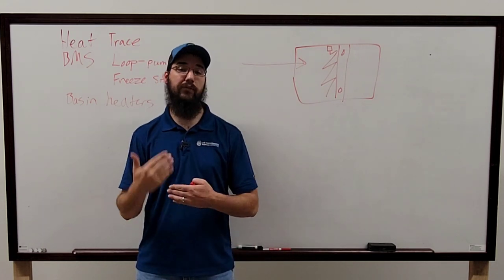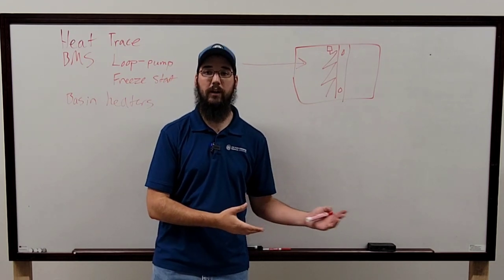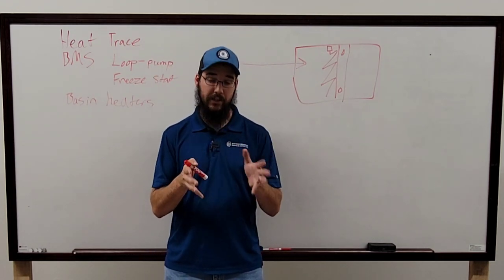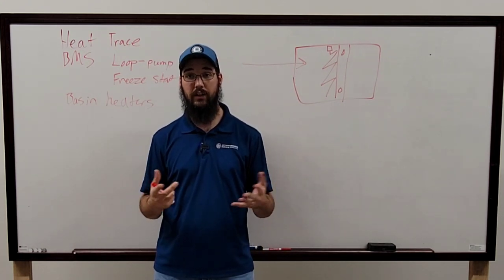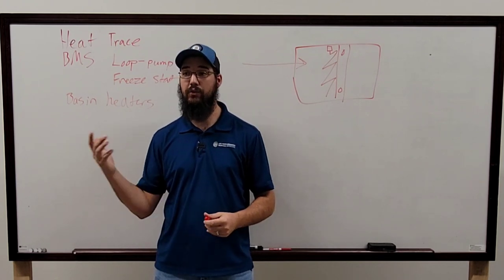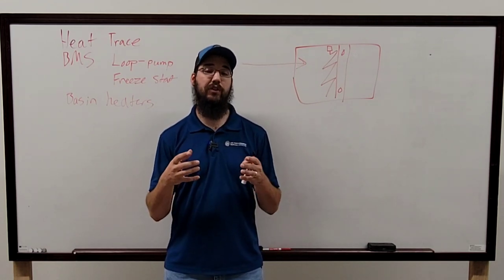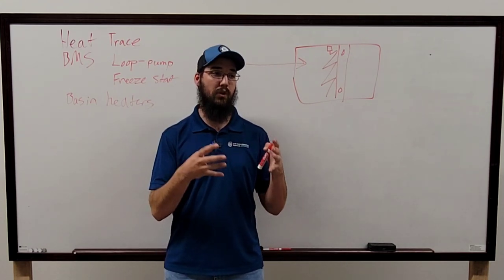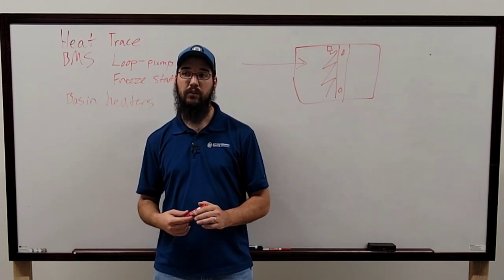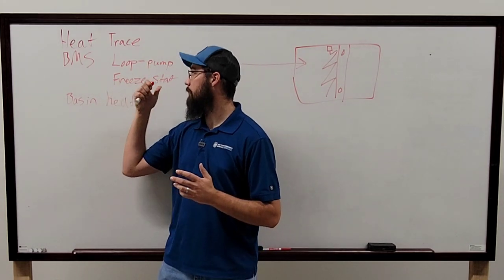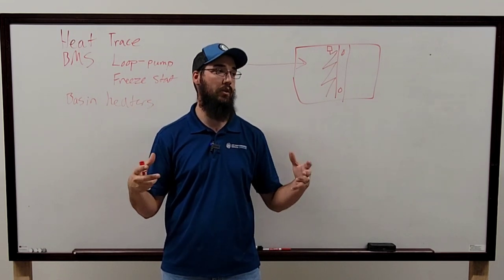The goal is to turn on the pumps and open all isolation valves, bypass valves, and any valves in the units — getting water to flow to anywhere it has the potential to freeze. That is the ultimate goal when automation kicks into freeze protection mode.